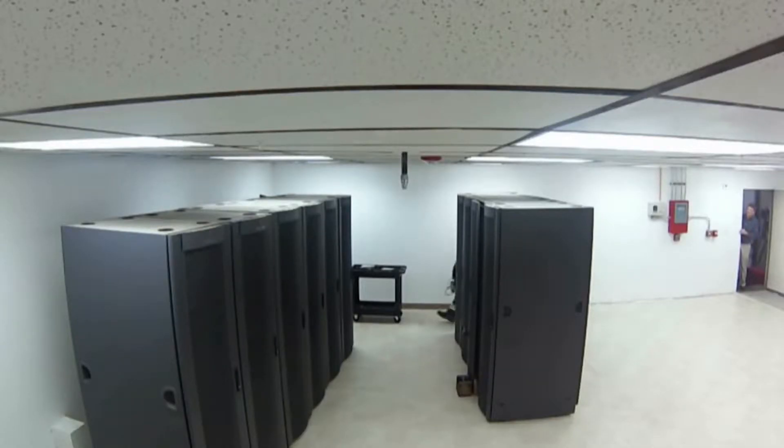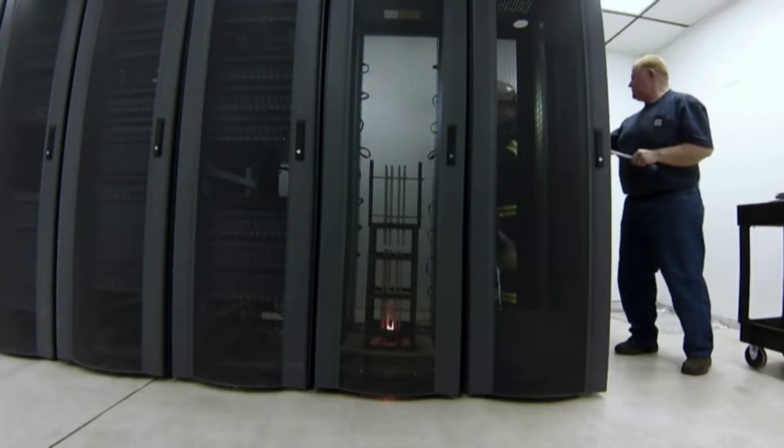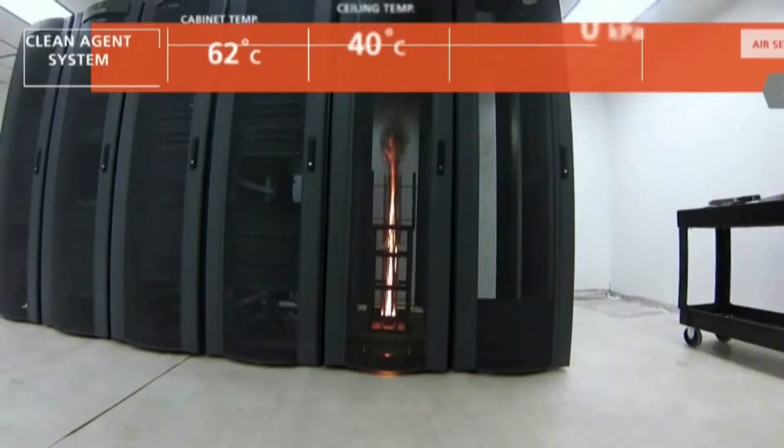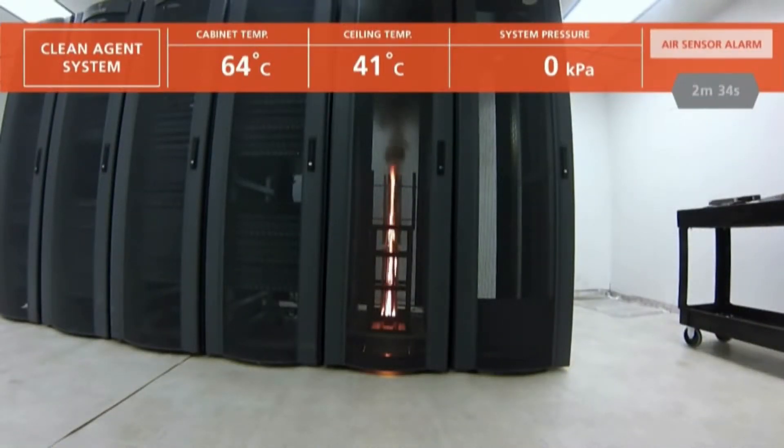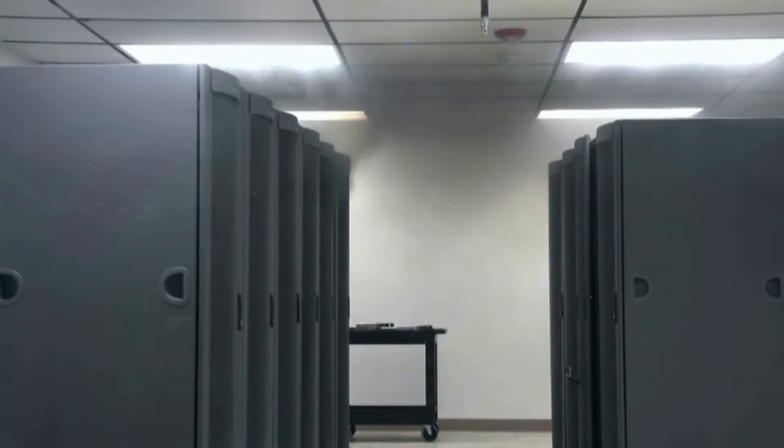When everything is ready, the clean agent test is run first. Engineers ignite sheets of ABS plastic in an empty server cabinet. The air sampling and spot smoke sensors alert the system.